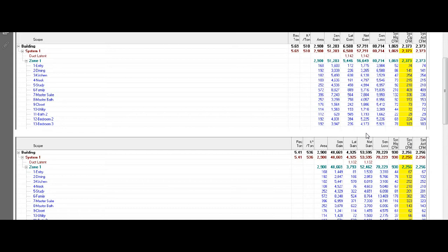And that's the benefit of the load calculation. It will give you that information. Now, it won't measure the amount of air infiltration in CFM entering the house, but the blower door test will do that. But when you know the amount of CFM entering the house, what do you do with that information? How much does it change your load? You don't know that. Only a load calculation will show you that. And in some climates, if you have some air infiltration entering a house, it's not as big of a deal. In other climates, it's a big deal. You need to stop the air infiltration.